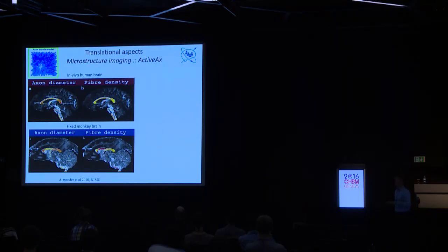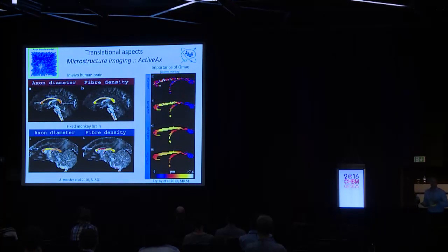So we investigated the impact of gradient strengths on these microstructural features, and because we have ex vivo, we can do very long scan times. When I say very long scan times, it's about 1 week or more. We used this protocol optimized with different gradient strengths of 60, 140, 200, and 300, to investigate how this impacts our microstructural model to estimate axon diameters. We can see that at about 200 to 300, we get robust estimates of axon diameters across corpus callosum. But if the Gmax gets too low, then we cannot really fit it and we cannot trust the results.